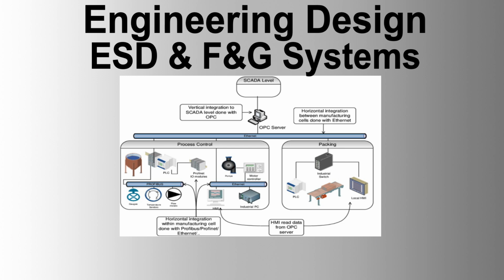Installation and integration. 1. System installation. Installation of the ESD F&G equipment must be planned and executed to minimize disruption to existing operations. The installation process should follow the provided installation guides and configuration manuals. 2. System integration. Integration with existing systems must be seamless, with thorough testing to verify functionality. The vendor must coordinate closely with other system vendors to ensure smooth data exchange and compatibility.